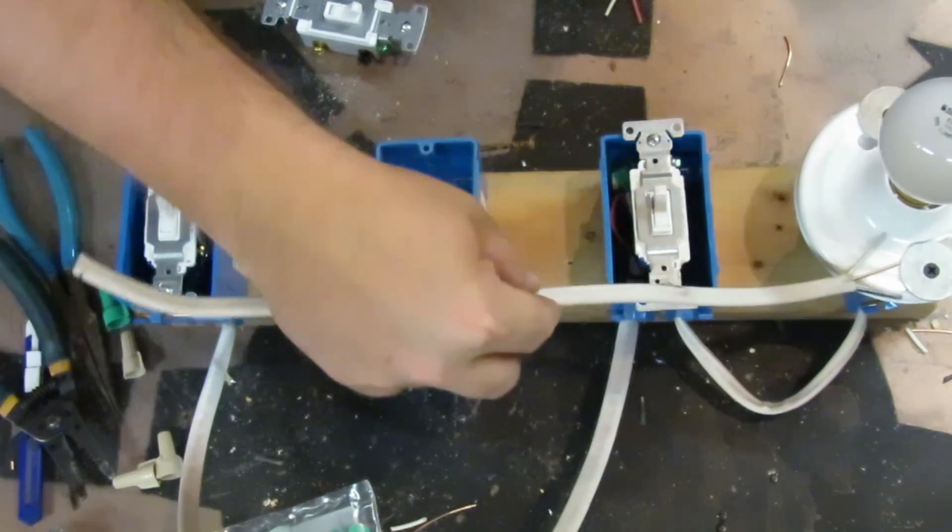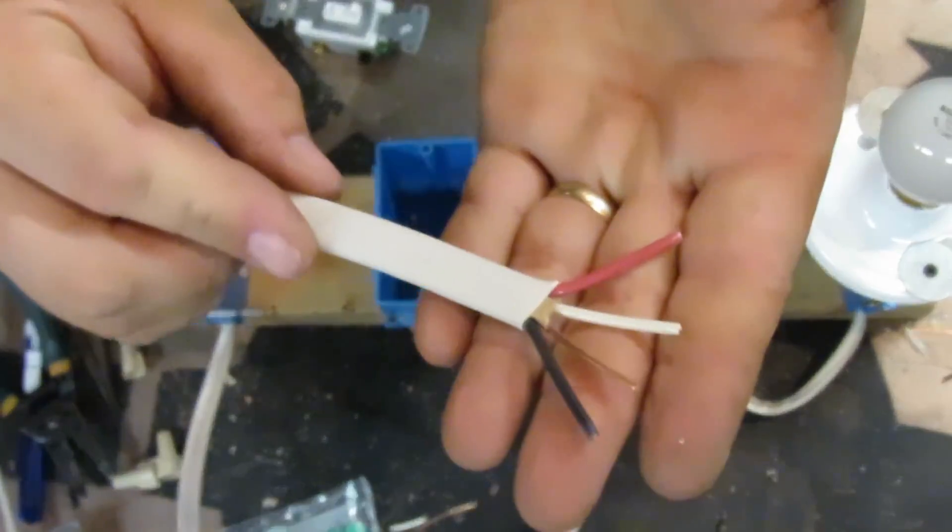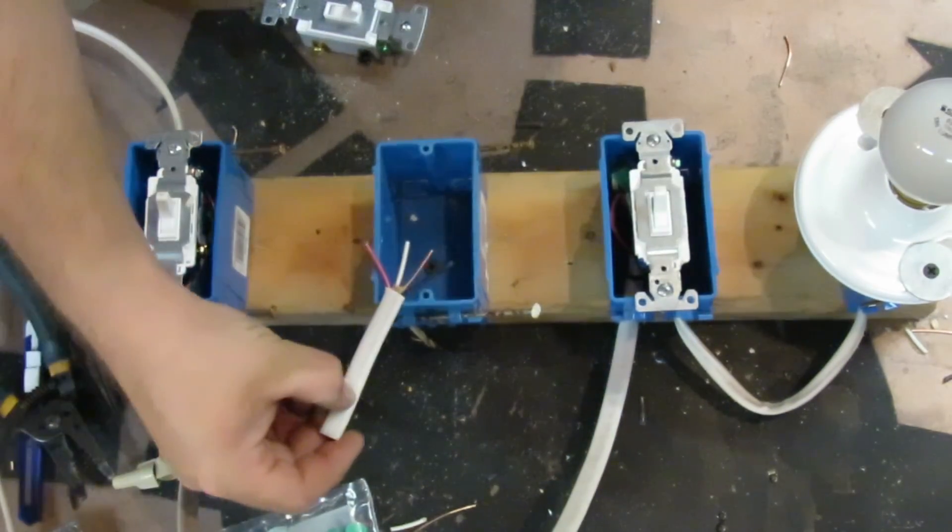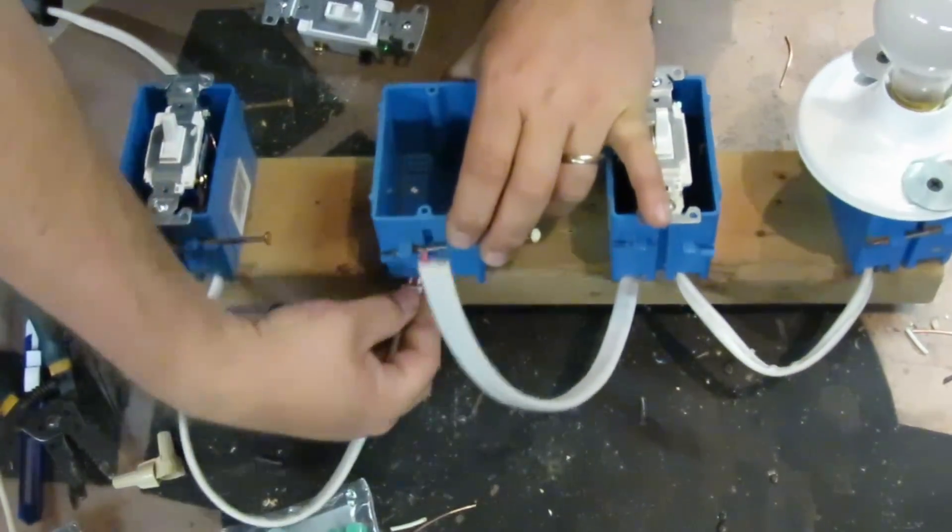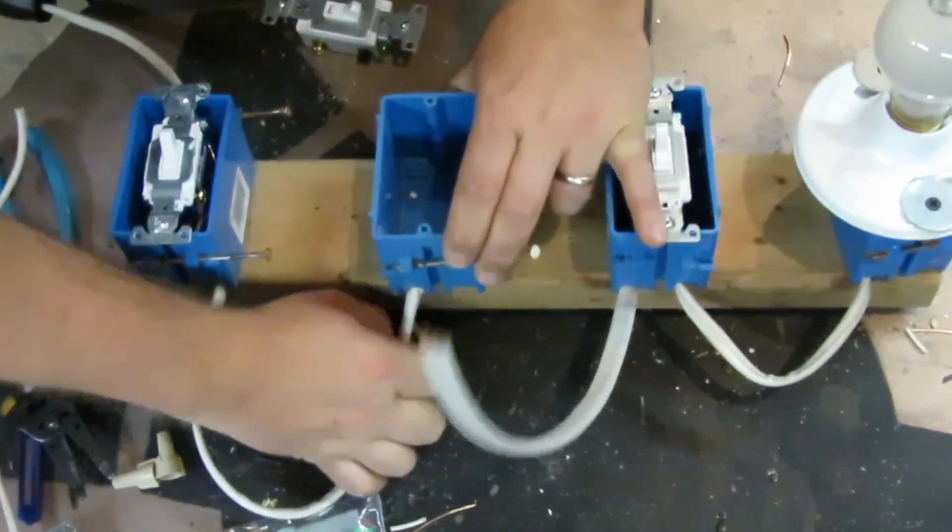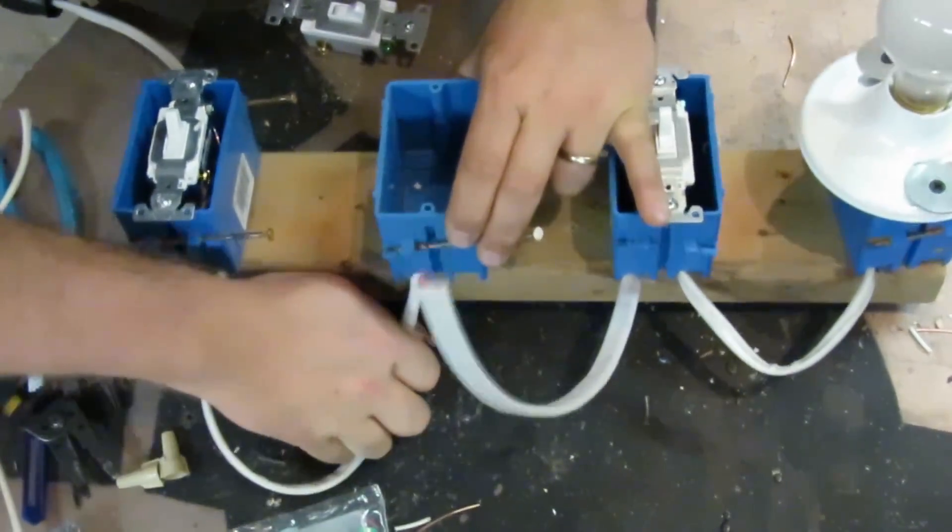This is a piece of 14-2 wire, and it goes for the power and the switch line. This is 14-3, and this is going to go between the switches. The difference between the 14-2 and the 14-3 is that the 14-3 has an extra conductor—it has the red wire.